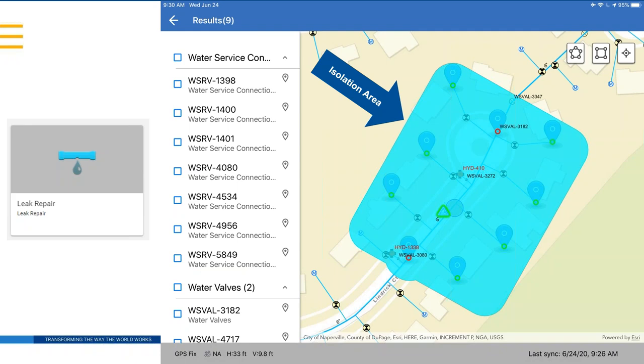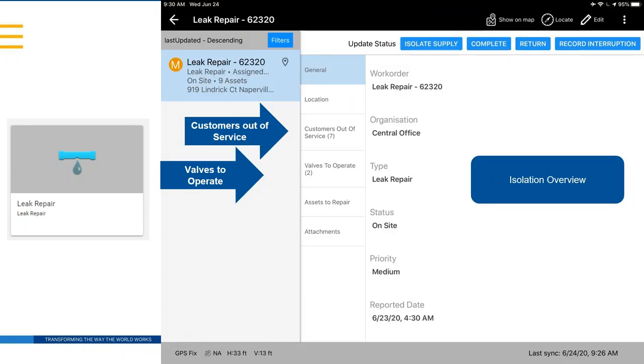After confirming the leak, the field person can perform a valve isolation. They touch on the map, Trimble Unity looks at the network as built, and identifies the valves that need to be turned to isolate that section of pipe. An isolation overview page appears — for example, it might tell you that isolating this pipe segment requires operating two valves, and doing so will take seven customers out of service.